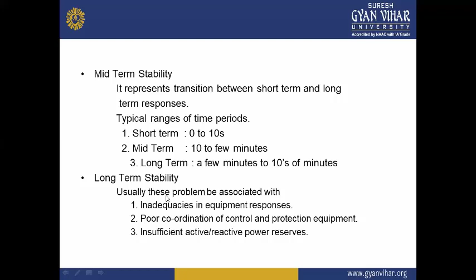Usually long-term stability is associated with inadequacy in the equipment responses. That means if the equipment is not giving adequate responses, that could be a cause of long-term instability, as well as poor coordination of control and protection equipment. That means coordination of protection equipment like relays and circuit breakers. If you do not have coordination between the relays and circuit breakers, and even between the primary and backup relays, then it will cause long-term instability. The third reason for long-term instability is insufficient active or reactive power reserves.